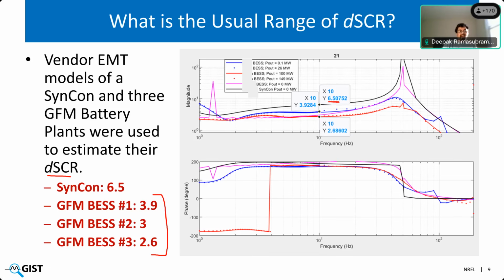That kind of operating point dependency is dependent on nonlinear elements in the control. It's not an aspect of the characteristic of the resource itself, but more about something similar to a limit or a saturation element playing a role. Yeah, and maybe one point I would like to add here is on why we use Q by V or P by theta scans and not something else. One reason is it has a good correlation with voltage jump and phase jump tests.